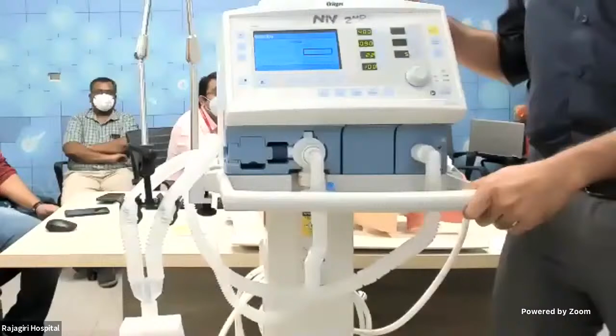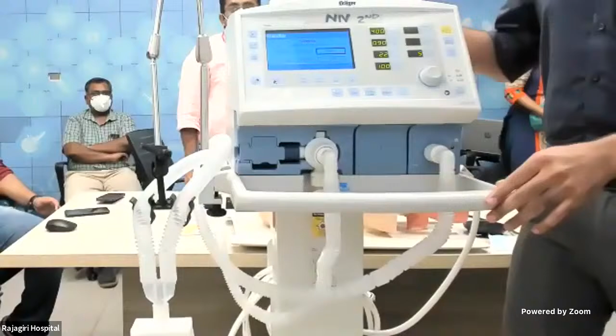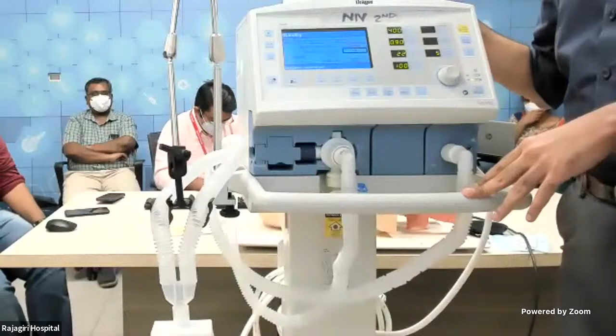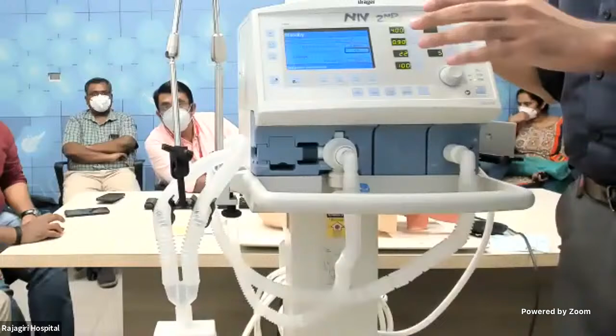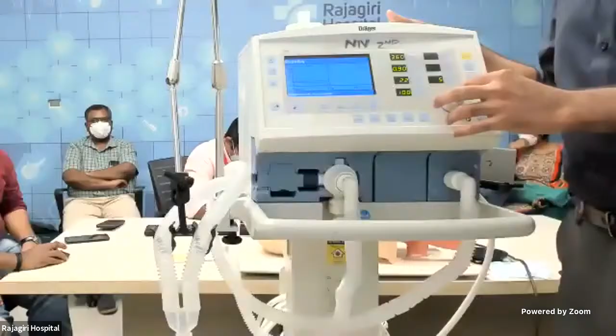Thank you, doctor. Okay, so here we have a Dräger machine. In each machine there are different setups and different modes, but basically I'm just going to explain two major modes: one is the volume control mode and the other is the pressure control mode. I've put this machine in volume control mode. The first thing we have to check is the tidal volume. As Dr. Jacob Suraj told us, we set a tidal volume of approximately 6 ml per kg. For example, if the patient's body weight is around 60 kg, 6 times 60 is 360, so we can fix a tidal volume of approximately 360.